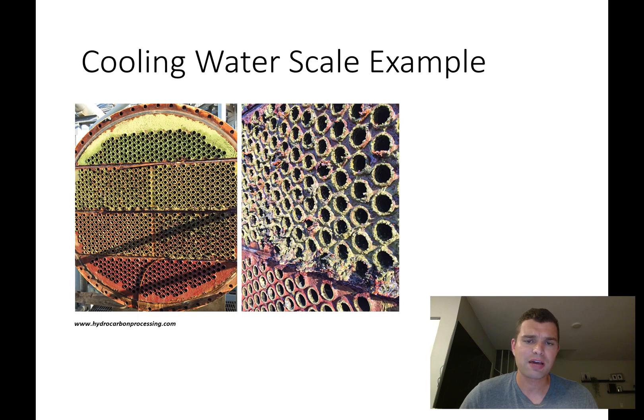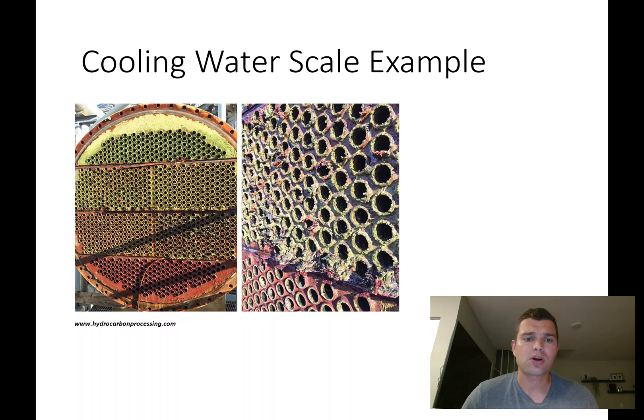Here's an example of what scale can look like. I've definitely seen scale worse than this and not as bad, but we've also seen cases where a majority of your tubes are plugged. Calcium carbonate can form rather quickly, and that all goes back primarily to your water hardness.